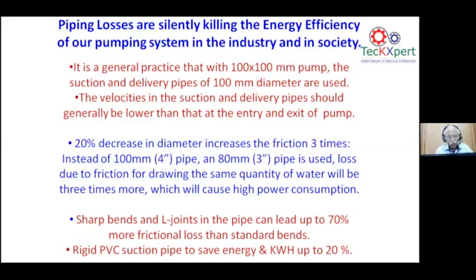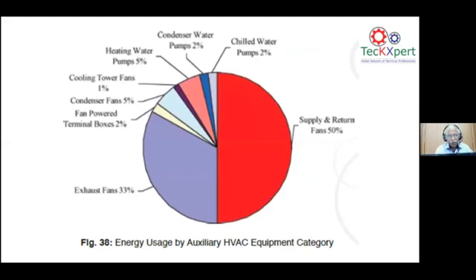Any of the sharp bends used in the piping increases friction by 70%. Friction loss is more as such. So with rigid PVC pipes on the suction and delivery, you can definitely see a straight away 20% kWh savings. Coming to the compressors, this is on the air utility side, the air compressor side.